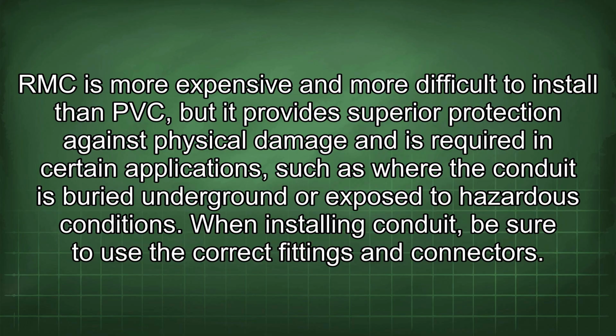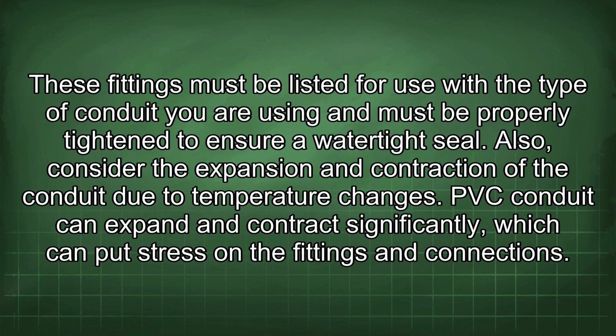RMC is more expensive and more difficult to install than PVC, but it provides superior protection against physical damage and is required in certain applications, such as where the conduit is buried underground or exposed to hazardous conditions. When installing conduit, be sure to use the correct fittings and connectors. These fittings must be listed for use with the type of conduit you are using and must be properly tightened to ensure a watertight seal.